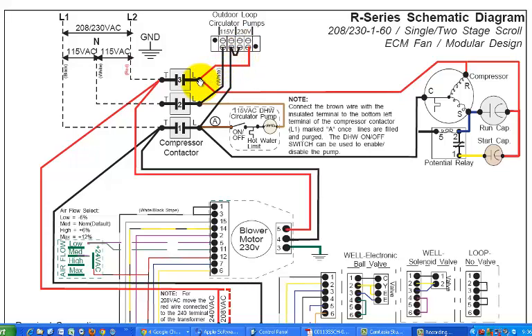And similarly, off the L2, we've also got that branching off and coming over and feeding this. So note that those are going to be hot again when the compressor contactor is pulled into play. So when that happens, we've now also got a 230 or so volt potential difference between those two terminals, and the electrician at that point can wire in the circ pumps to those terminal points. And of course, what's going to happen is that they're going to actuate when the compressor is brought into play, and I guess also only actuate when the compressor is brought into play.